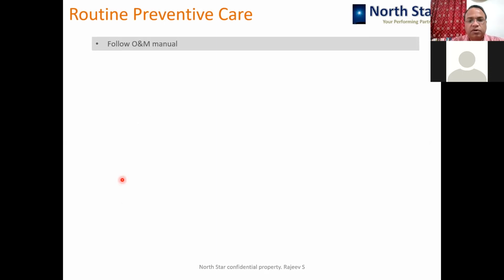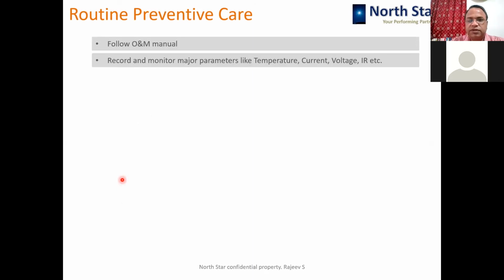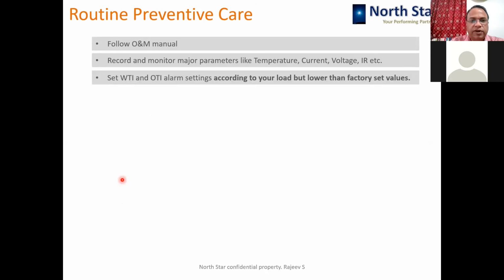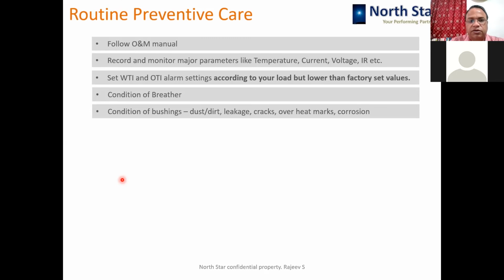One is to follow the O&M manual, which is the Bible for the transformer user. Record major parameters. We talked about data monitoring over here. Again, OTI, WTI alarms to be set according to your load, not as per the factory set values. Condition of breather, condition of bushings: dust, dirt, leakage, cracks, overheat marks, corrosion, all is to be taken care of and attended to on time.